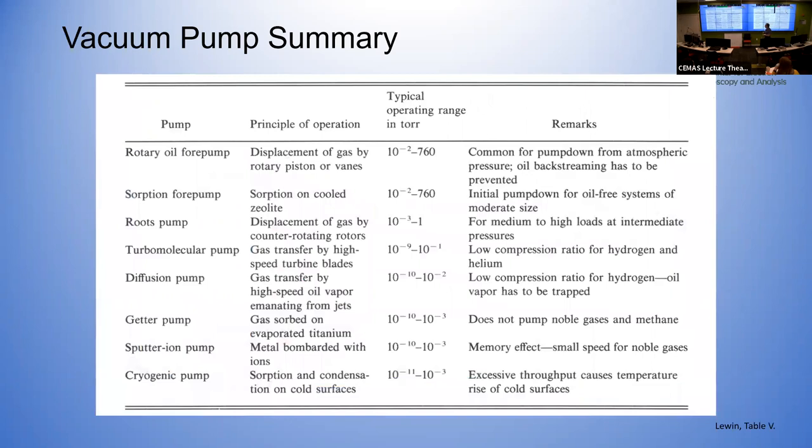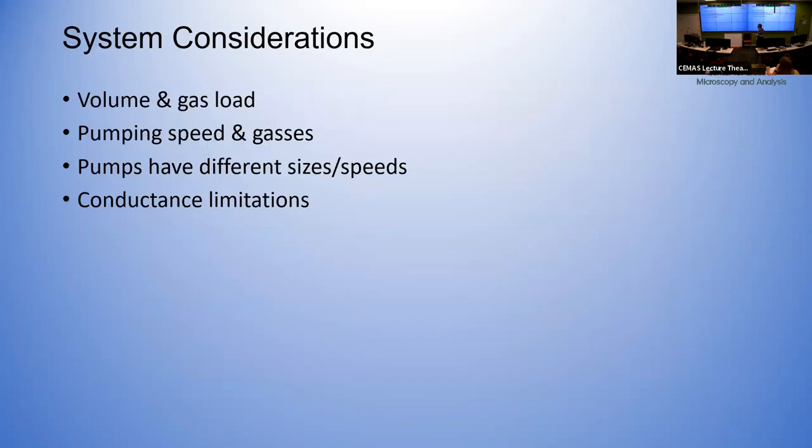There's another type of entrainment pump called a cryo pump. So here you're cooling things down to liquid helium temperatures, a few degrees Kelvin. When you get down to the condensation point of a gas, you can adsorb those gases onto surfaces very well by the van der Waals forces. So they will use activated charcoal or something to give you a nice surface area here. And then they have various cooling elements at different temperatures. So water vapor, I mean, that'll condense at a very high temp at a relatively high temperature. But if you want to get down to helium or hydrogen, you need to be down in the few degrees, few kelvins range. And again, these are entrainment. So they trap the water vapor or the gas in the pump. The difference between this and an ion pump is that you valve this one off, you let it warm up and all the gas comes off. So you then have a roughing pump that'll pump away the gas. You cool it down again and start all over. So to summarize, there are a number of different pumps. And this is from the book by Lewin and with some of the comments about strengths and weaknesses of different types of pumps. And if you're interested, I can, I have the book and I can let you take a look at that.